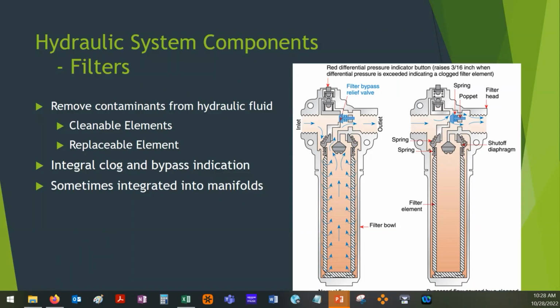But they live inside of a bowl, so you can see these cutaways here. Pressure comes in, travels on the outside of the bowl, goes through the wire mesh into the middle, and then comes up and out the outlet. However, over time, if this mesh starts to get clogged, or if something catastrophic clogs it, there is a bypass valve up here, a little poppet valve. If the pressure on the inlet is significantly higher than the pressure at the outlet, it will force this valve open, and instead of going through the filter, the fluid just bypasses. You lose filtering ability, but the system's still able to run. Okay?